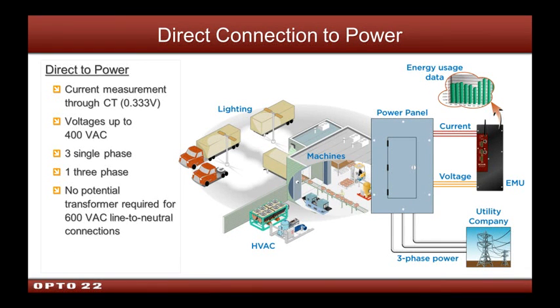They have actually a voltage output. It's 0.333 volts. So you have, of course, your primary current on the primary side, and on the secondary, instead of having a current on your secondary, you have a very small voltage, which is what facilitates them being smaller and less expensive. So very common out there, and again, we support the 0.333 volt CTs. So you would bring that signal as well as your voltage into the OptoEMU sensor.